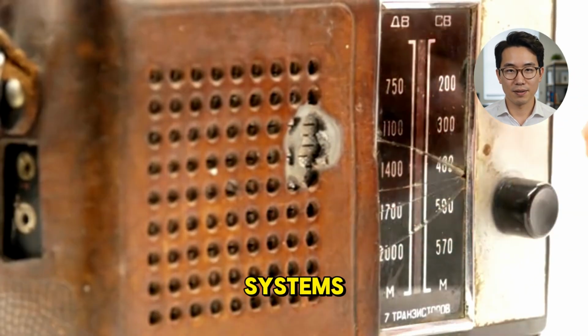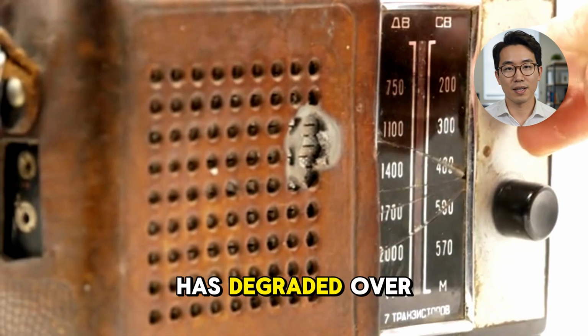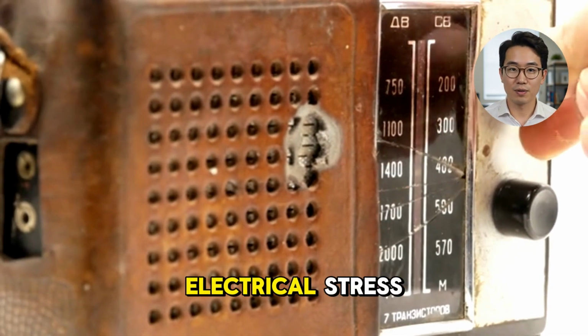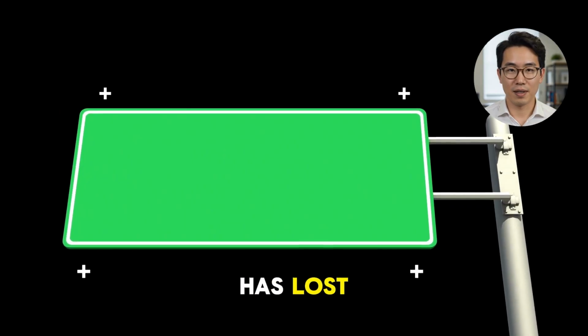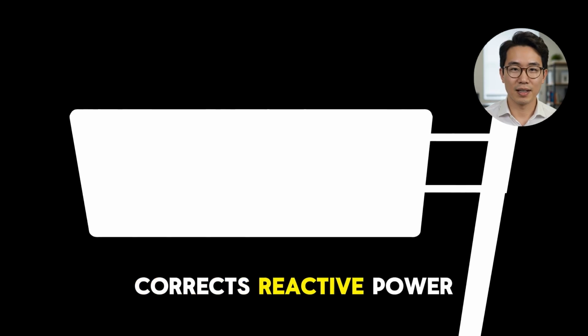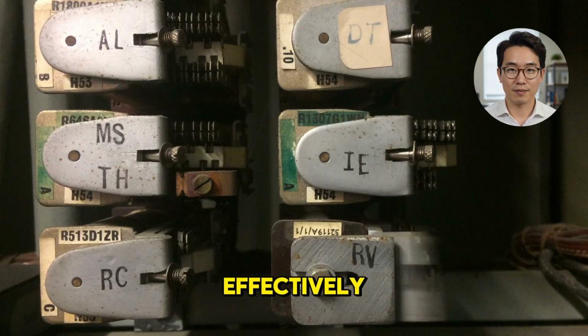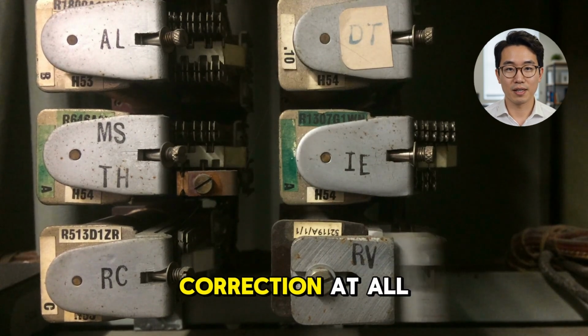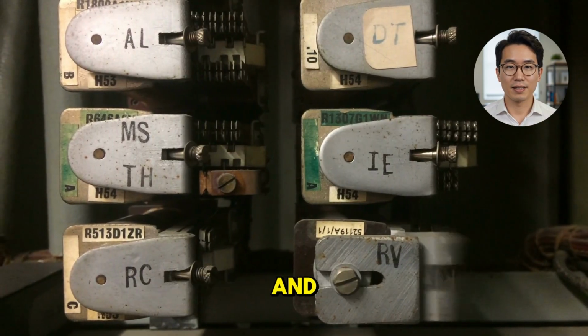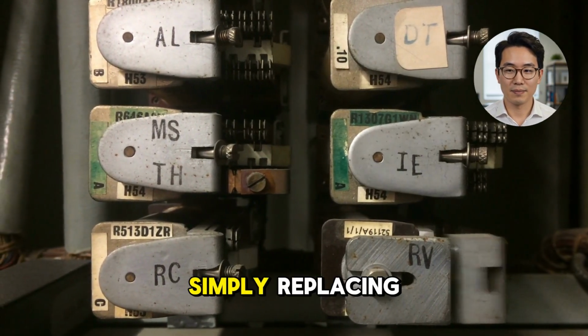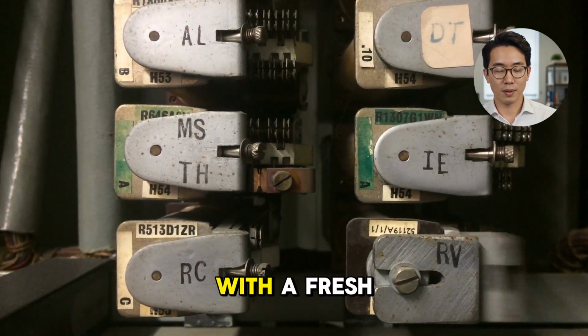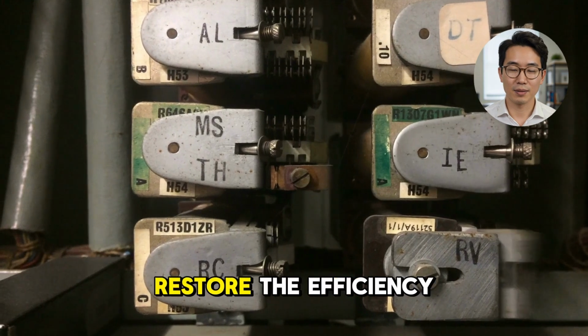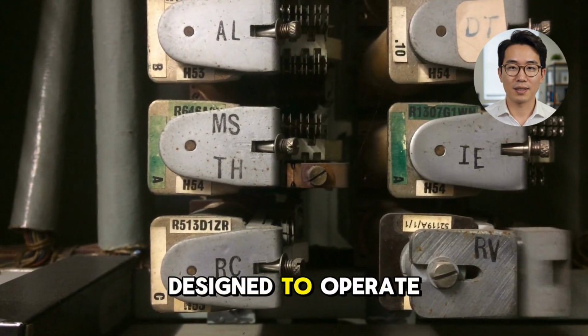In many older systems, the original run capacitor has degraded over the years of heat cycling and electrical stress. A capacitor that has lost capacity no longer corrects reactive power effectively. The motor is effectively running without power factor correction at all, borrowing reactive current and sending it straight back to the grid. Simply replacing a degraded capacitor with a fresh one of the correct rating can restore the efficiency the system was designed to operate at.